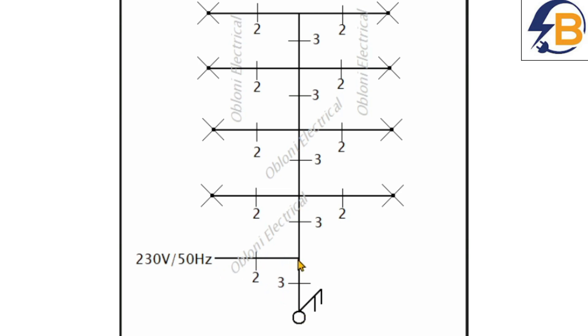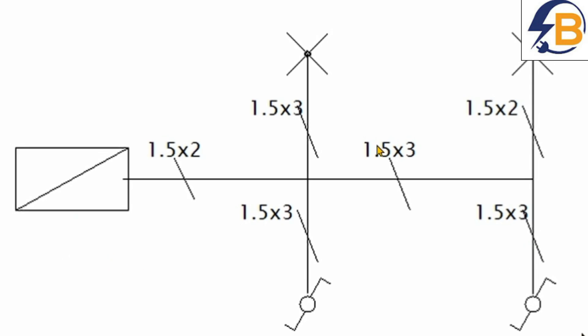If you observe this drawing carefully, you'll realize these are a two-gang switch. The three wires that pass here: one feed that comes in, and then two switch wires — because there are two gangs, one wire connects to one gang and the other wire connects to the second gang. One switch wire supplies the lamps on one side and the other supplies the lamps on the other side. When you come here, we have two switch wires and a neutral wire. There's probably a junction box here where we take one neutral in one direction and the other neutral in the other direction, looping switch wires and neutral wires to the next lamps.